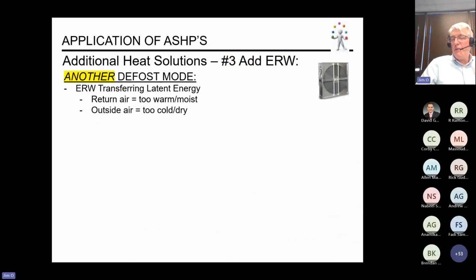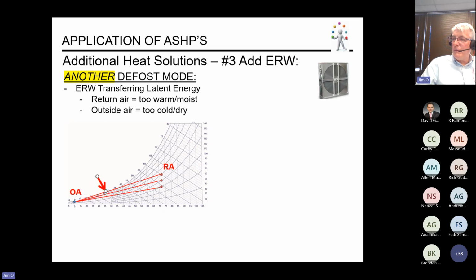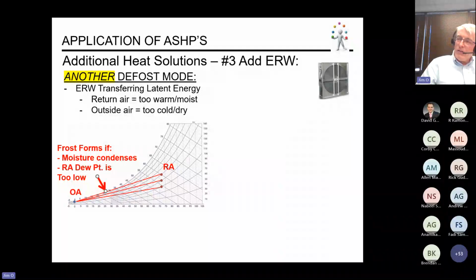Also, with your energy recovery wheel, you have to be aware that there is a second defrost mode associated with the energy recovery wheel. What will happen is if our outside air temperature is too low and our return air is too moist, as the wheel turns and the air from one airstream enters the other, the moisture on that wheel could form and condense out.